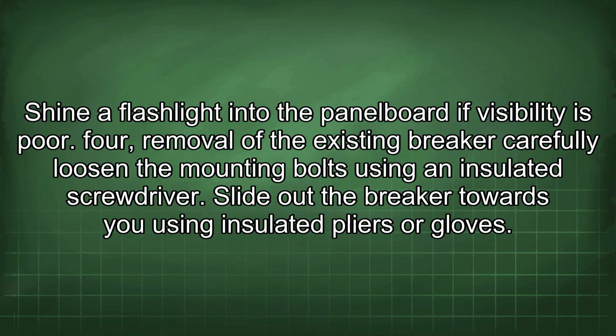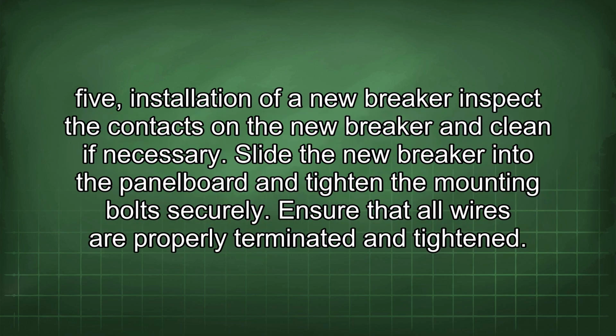4. Removal of the existing breaker: carefully loosen the mounting bolts using an insulated screwdriver. Slide out the breaker towards you using insulated pliers or gloves. 5. Installation of a new breaker: inspect the contacts on the new breaker and clean if necessary. Slide the new breaker into the panel board and tighten the mounting bolts securely. Ensure that all wires are properly terminated and tightened.